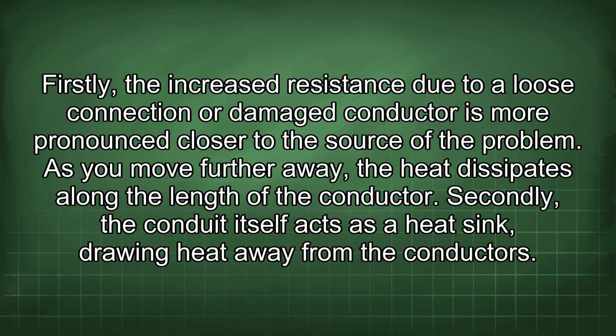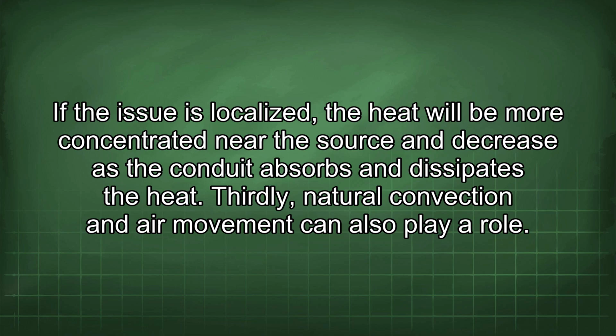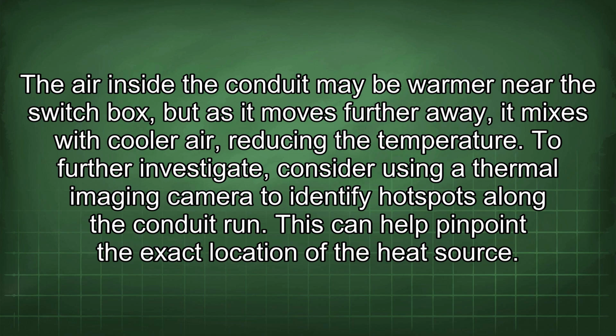Secondly, the conduit itself acts as a heat sink, drawing heat away from the conductors. If the issue is localized, the heat will be more concentrated near the source and decrease as the conduit absorbs and dissipates the heat. Thirdly, natural convection and air movement can also play a role. The air inside the conduit may be warmer near the switch box, but as it moves further away, it mixes with cooler air, reducing the temperature.